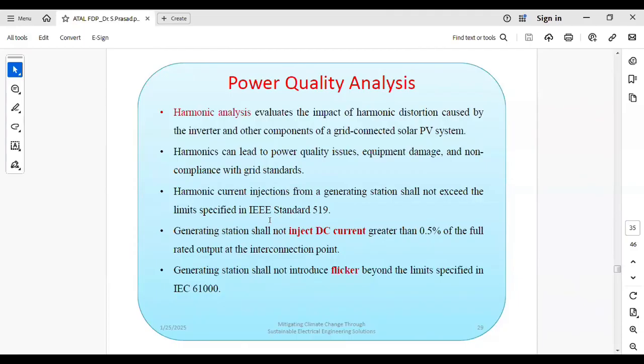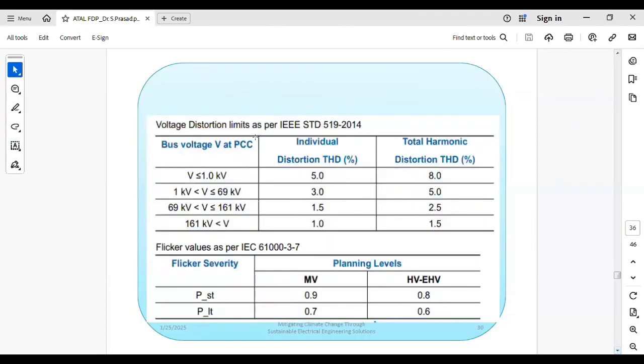So this is power quality analysis at the point of interconnection, and you have to generate a report for power quality analysis of a grid connected solar PV plant and submit it to the CTU, the utilities, for verification and for getting approval. If you comply with the grid code, then you will get the approval and the permission to go for interconnection of the PV plant to the grid. And these are the voltage distortion limits as per IEEE standard 519 2014.